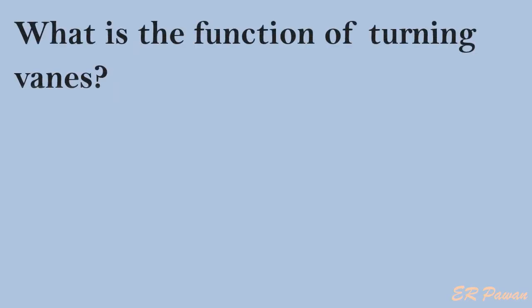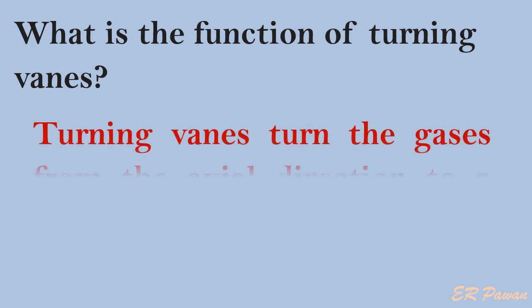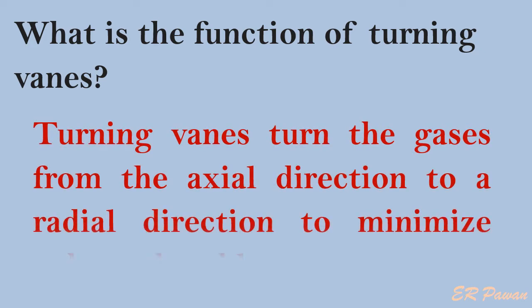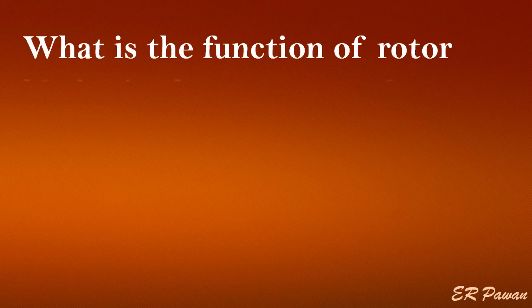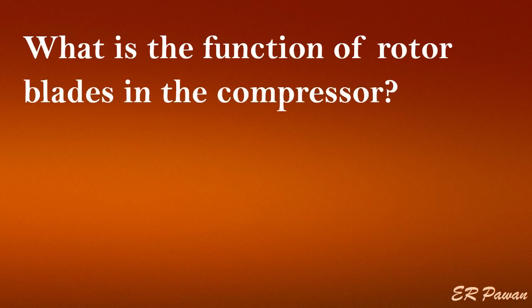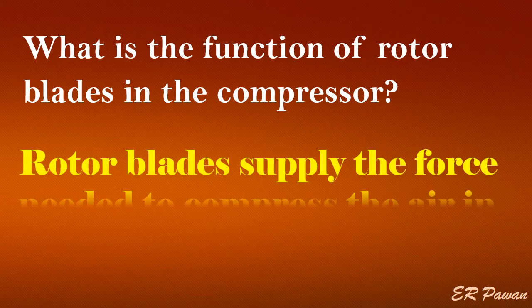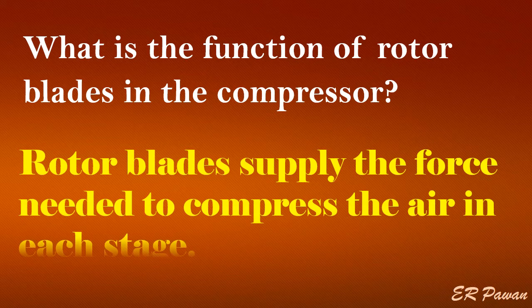What is the function of turning vanes? Turning vanes turn the gases from the axial direction to a radial direction to minimize exhaust hood losses. What is the function of rotor blades in the compressor? Rotor blades supply the force needed to compress the air in each stage.